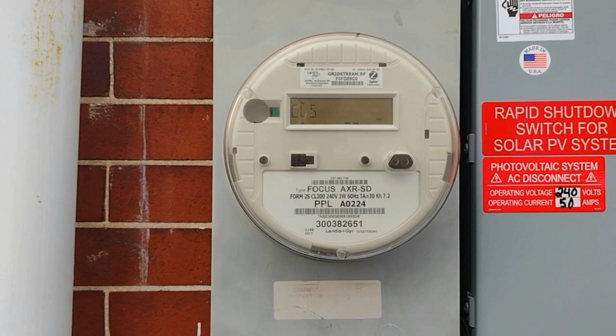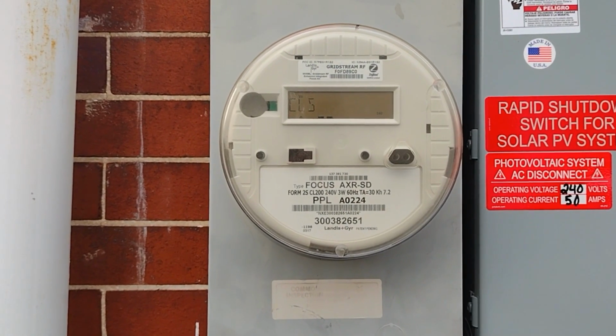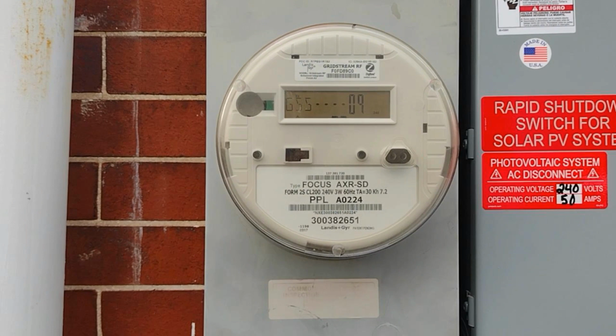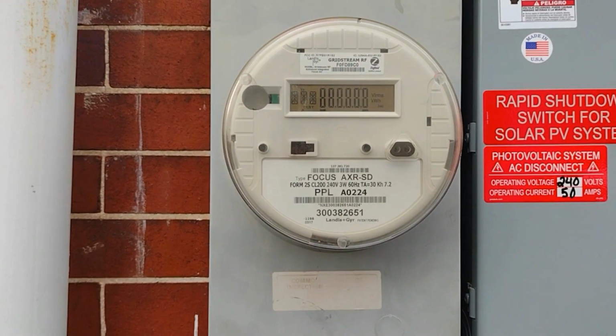The next screen is going to be your closed open screen. This is going to say whether the internal power switch that's built into your meter is allowing power to go through to your house or not. Next screen is going to say GSS, and that is more of a communications version, software version. It's kind of used for troubleshooting for PP&L. It's not anything that we can really use because it's something that they reflect on from their end. And then the final screen is the test screen. This is where everything lights up. All of your dots, dashes, letters, and everything on the display that's supposed to be working is working, so that you don't have like a 9 looking like a 4.